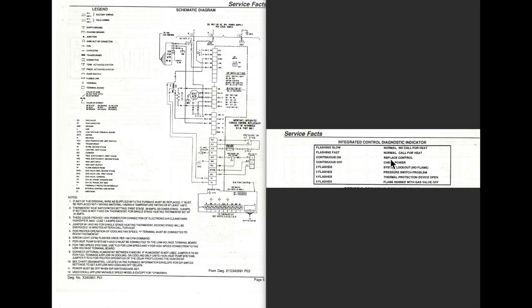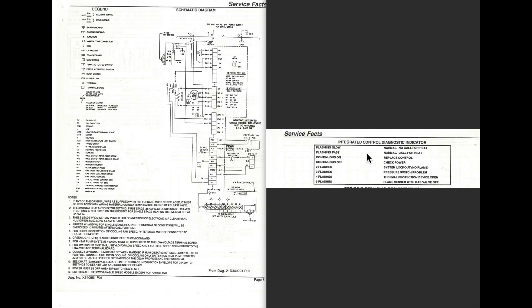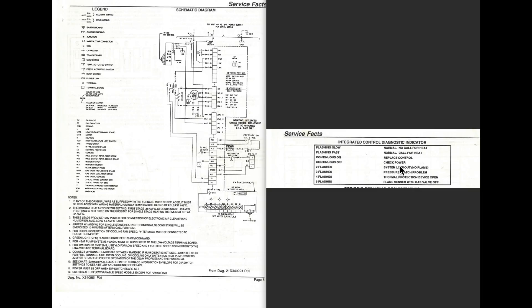Continuous on means you replace the control. What that means is the control's dead. These things test themselves every second or so. They run a circuit through it. So it's failed to run the circuit through it. And instead of flashing slow, like saying yep, we're fine, it's continuous on. So somewhere the sequence has stopped. Continuous off, check power. It's 24 volt controlled. So it doesn't mean power to the furnace isn't there, although it certainly could be. It means you don't have 24 volt power.